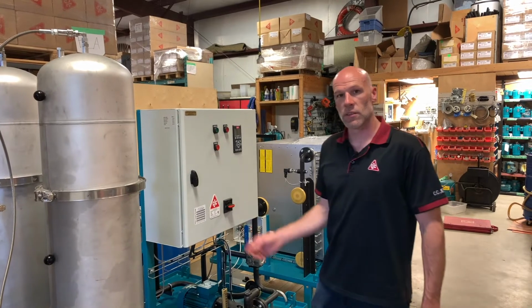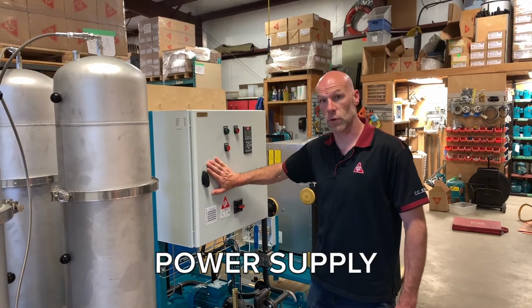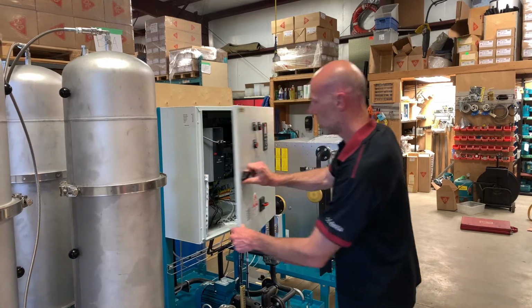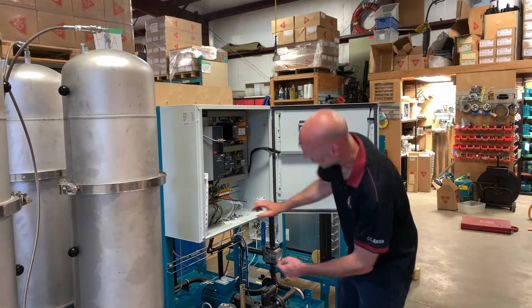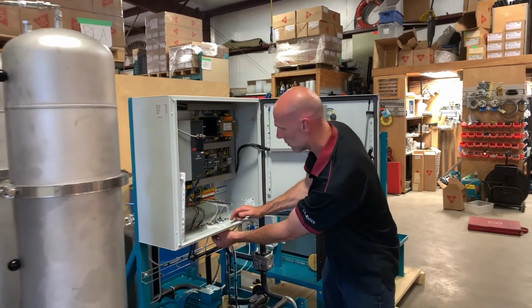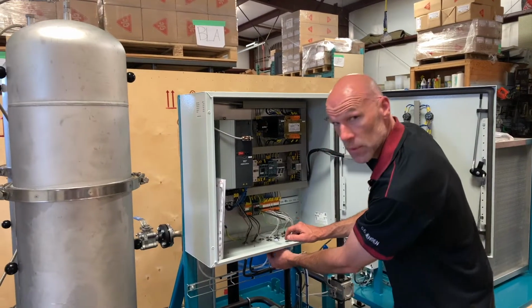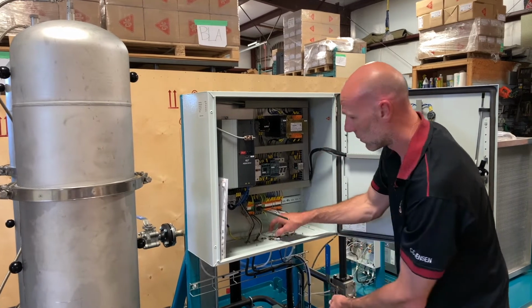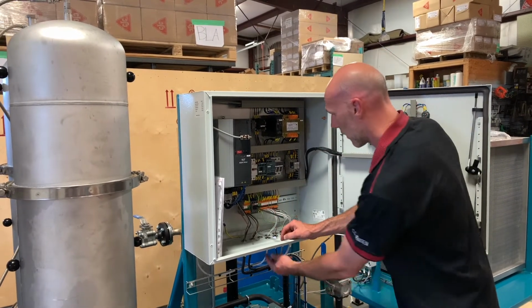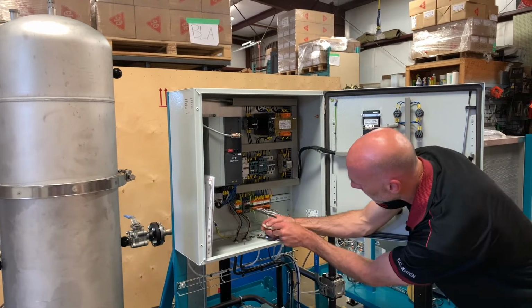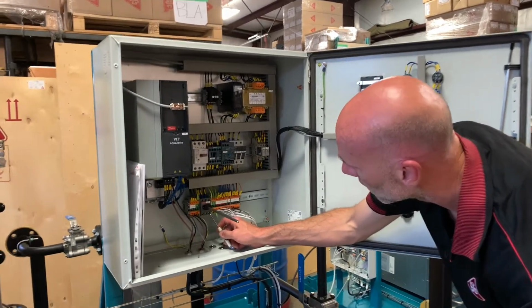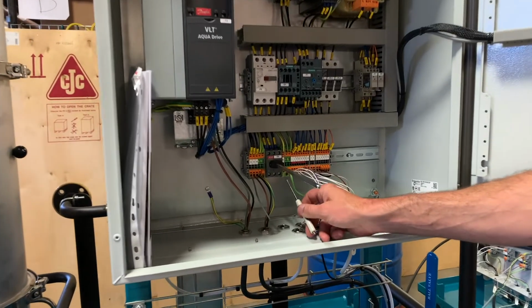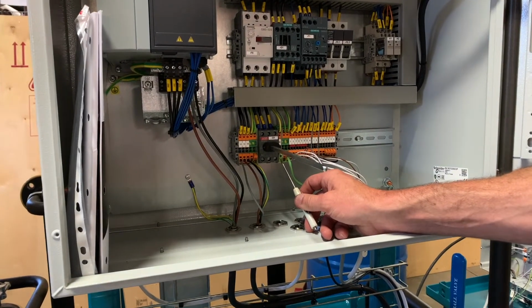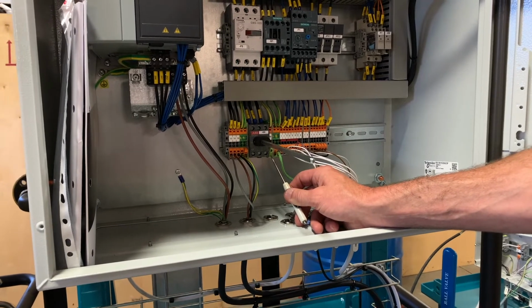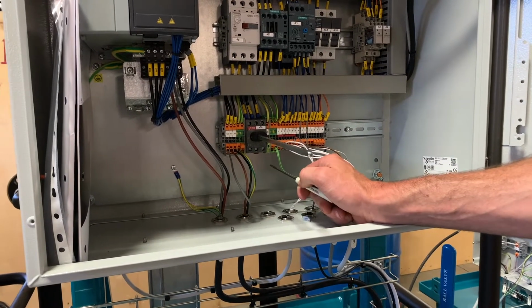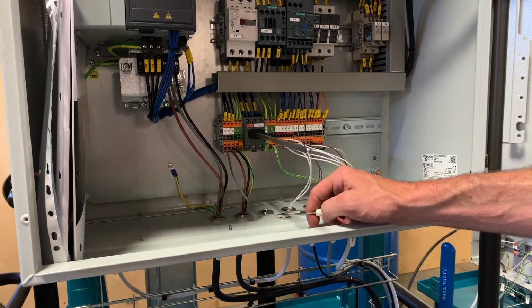Okay. To connect the electrical to the main panel, this is your source supply, and you'll open the door. You'll find extra strain reliefs located in the bottom that you can run your feed into. Might be that your cable that you're going to use is bigger than what's here, so feel free to take one of these out and knock it out to a larger size. When you run it up, you'll run it into the 3 terminals here on the switch. This is the main disconnect, and run a ground into the big ground lug here, and that'll have your supply. And you need to use a 575 volt 3-phase externally fused with a max fuse rating of 25 amps.